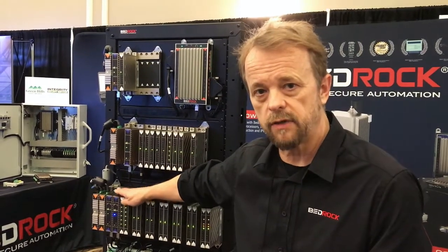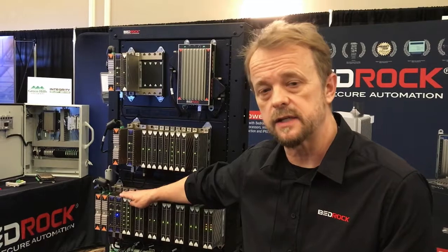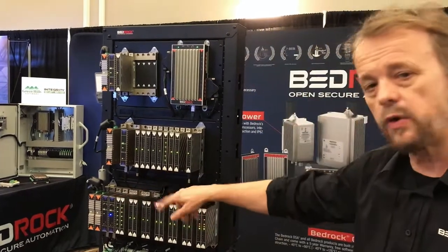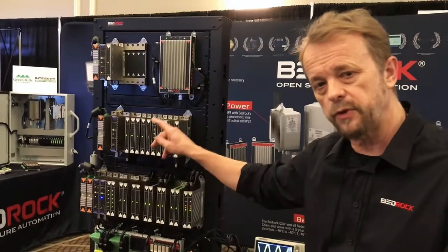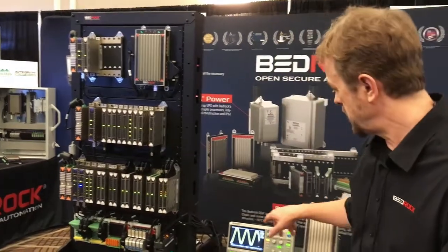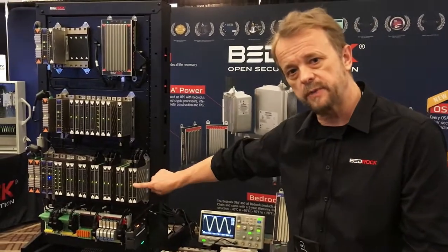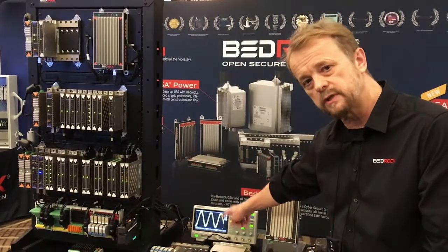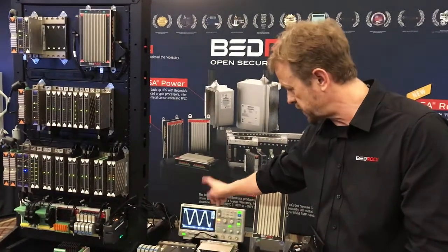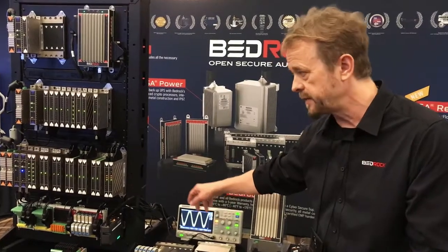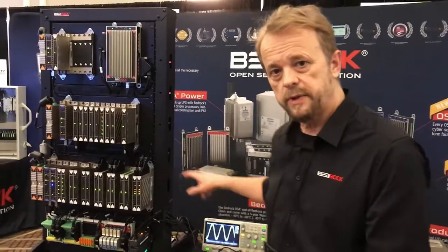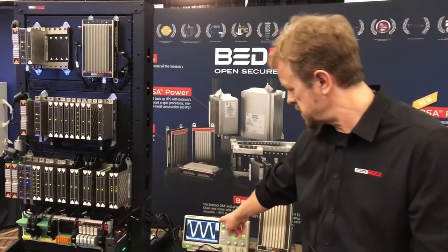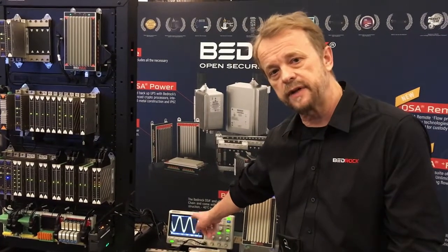And you'll see through the entire cycle how fast it is, and the fact that through the whole cycle of a firmware upgrade of both the primary and secondary controller, the inputs and outputs of this module have been tied back to the output. So in this oscilloscope, it's monitoring the 4 to 20 milliamp signal. It's going from 0 to 100% back and forth. And the importance is that you'll be able to watch the signal, which is sent to an actuator, a valve, at that speed, with a controller that's running its database at a 10 millisecond refresh rate.